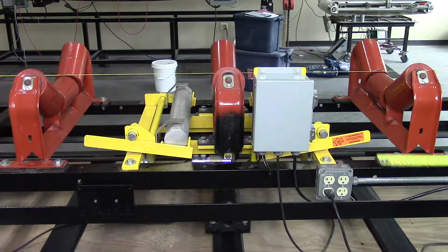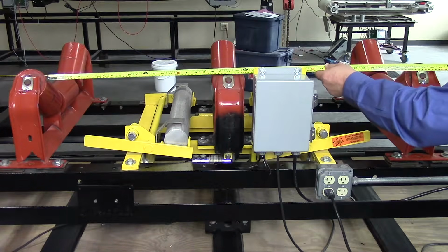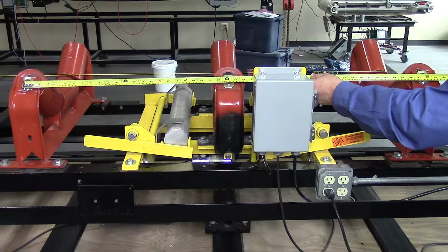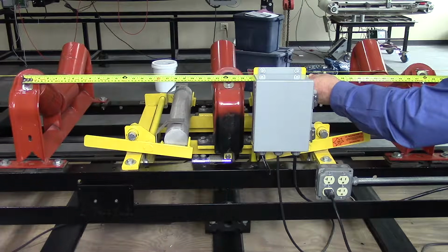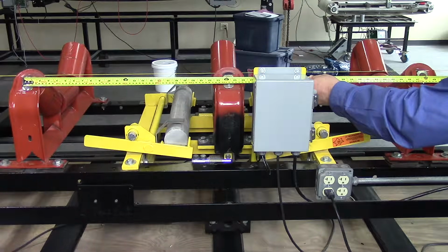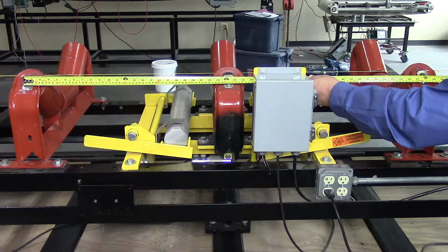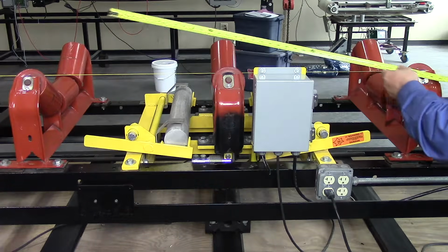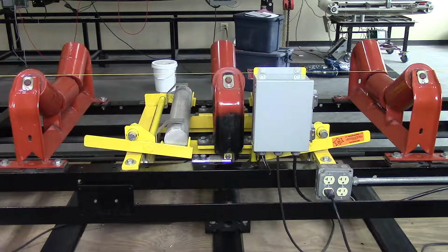Tecweigh electronics typically come already programmed with the scale sizing data supplied at the time of purchase, but it's good to check and verify the key parameters, especially the calibration weight, weigh band, which I'm doing here, as well as belt length values, just to double check and make sure everything is exactly what it's supposed to be. You'll have a much better installation if you do that.